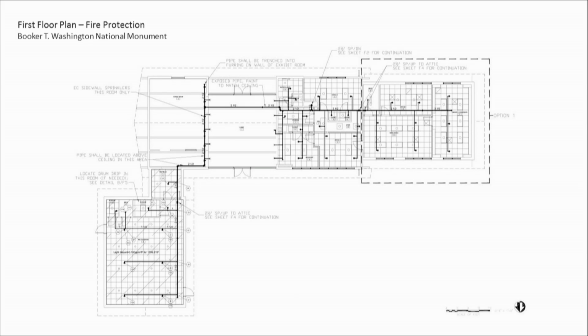The park staff wanted a wet pipe system to avoid the annual valve testing and maintenance required in a dry pipe system. We looked at ways of achieving the required climate control in the attics in order to provide a wet pipe system there. They really proved impractical, and a two-part system with dry pipe in the attic and wet pipe on the main floors really maximized first cost for construction while basically not alleviating the need for that annual maintenance.